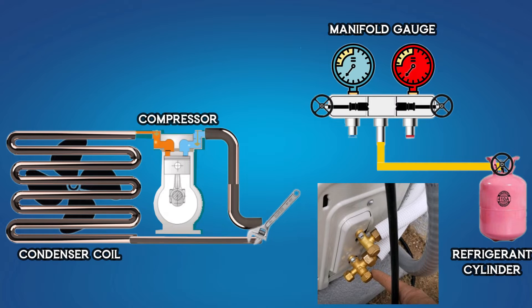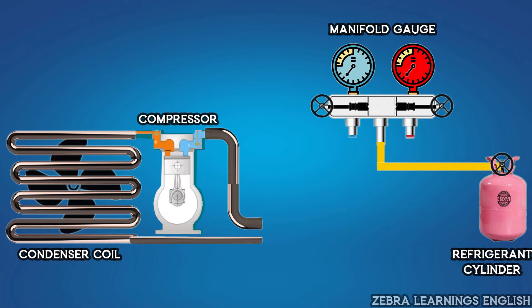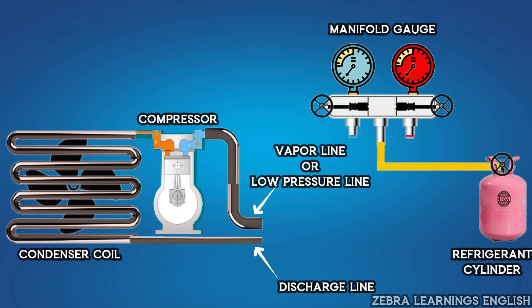Then, connect the low-pressure hose from the manifold gauge to the suction line. The larger size coil is the suction line and the smaller size coil is the discharge line. Suction line is also known as vapor line or low-pressure line. Discharge line is also known as liquid line or high-pressure line.